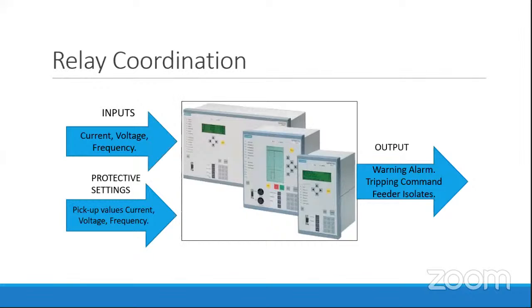So these relays provide a tripping contact at the time of the fault. They sense the fault and issue a tripping command to the switchgear. Compared to modern relays, the electromechanical relays were sluggish in operation, and many times they were very slow to detect the fault condition. So nowadays, with the help of modern technology, these relays are getting modernized into the numerical relay or IED relay, meaning intelligent electronic device.